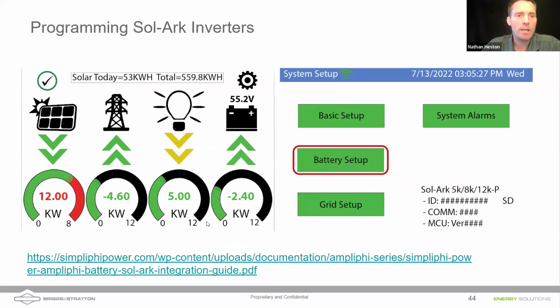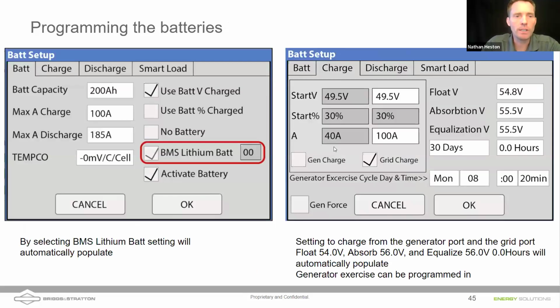So when you are programming a CAN bus enabled battery, if you're programming these communicating 6.6 batteries with a Sol-Ark, the setup becomes quite easy. There are some things that you do in the basic setup, enabling the screen timeout, for instance, etc. But once you get into the battery setup on the programming side of things, it's fairly easy to do. There's not a whole lot you need to do with communicating batteries. You need to check this BMS lithium battery, and the default there of 00 is fine for the SimpliPHI batteries. You'll put that overall capacity in so that it is communicated from the BMS, but in the event that you were to lose communications, you'll have that.